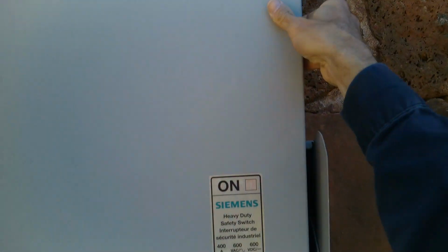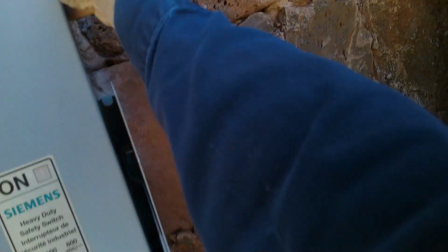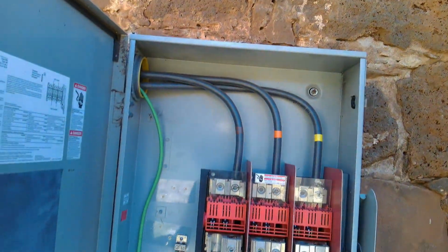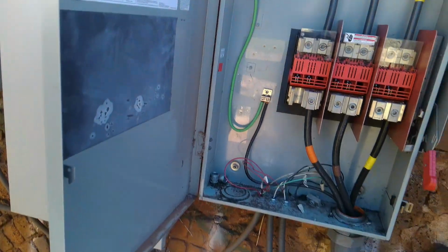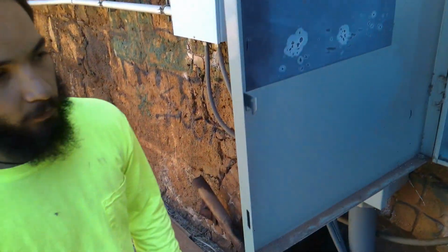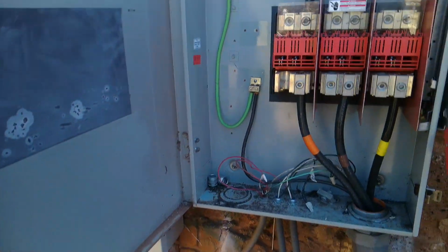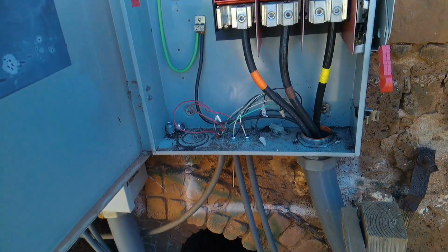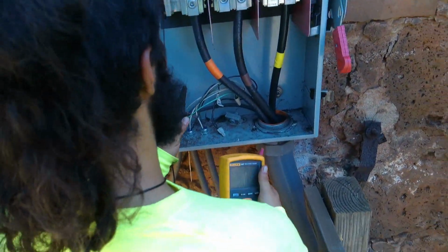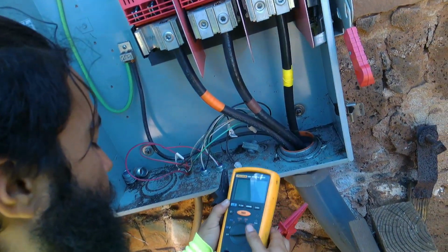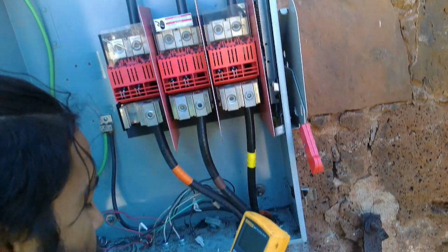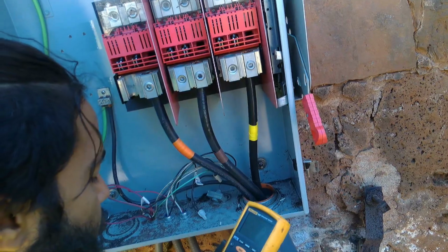cables down there and see what it shows us as far as resistance levels. Do you know what that megger does? It'll charge up a wire and it'll measure ohms. So it's basically an overpowered continuity checker. So what you're going to do, you're going to stand over here. You're going to put the megger in, you're going to take this probe and put it over onto insulation. Good. All the way in.